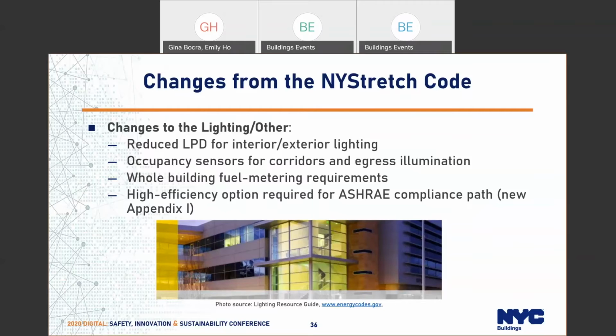All right, and then this is the last slide I have for changes coming from the stretch code. So again, the lighting power densities were reduced significantly from the state code for both interior and exterior lighting. The majority of these lighting power densities were developed for ASHRAE standard 189.1. And I think all but 4 spaces were adopted by New York City from the stretch code requirements. So, you've been hearing me talk about how lighting has greatly reduced. If you're a lighting designer, you definitely need to pay attention to these new lighting power densities. If you're an energy modeler and you're used to having a lot of savings for lighting, that is not going to happen anymore. So, this is a really good change in the code, we feel, but something definitely needs to be paid attention to.